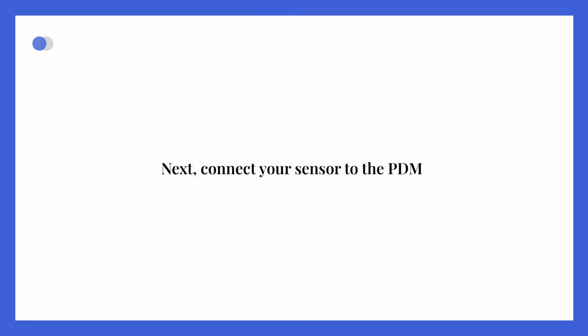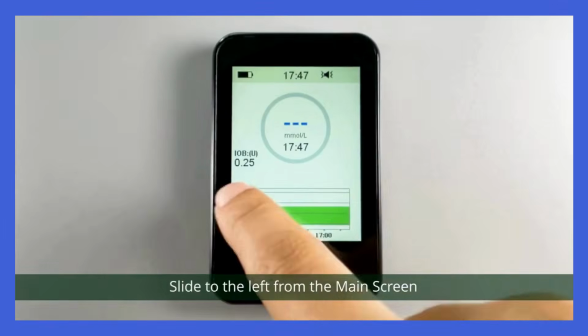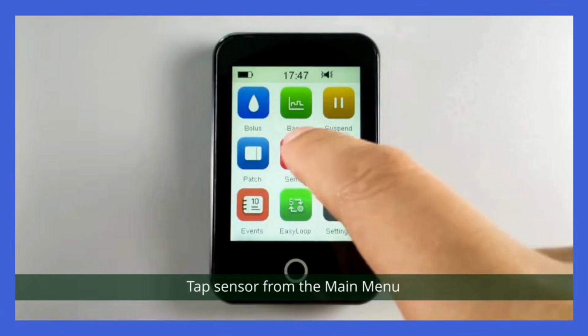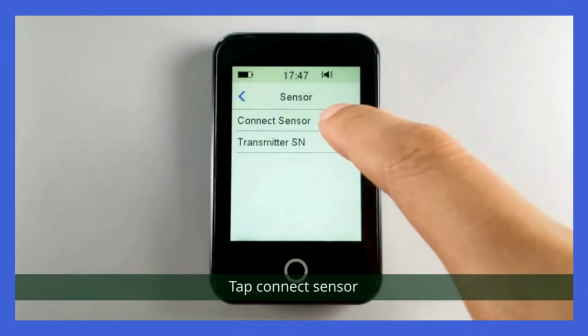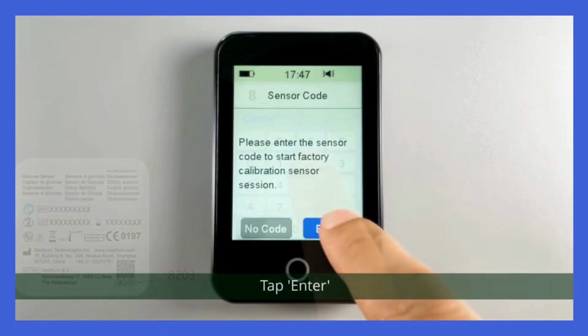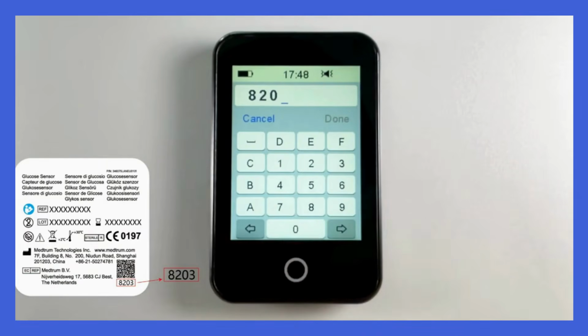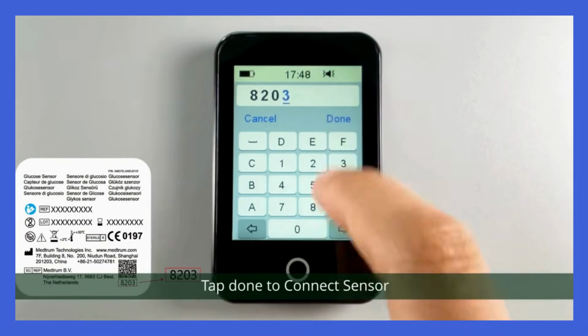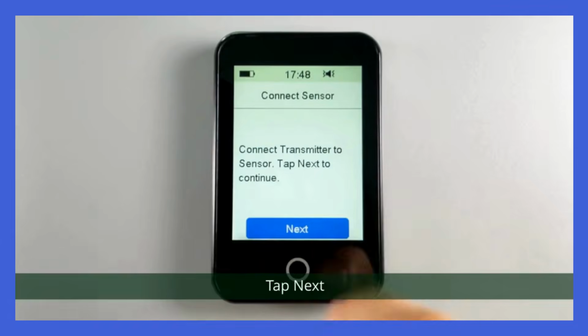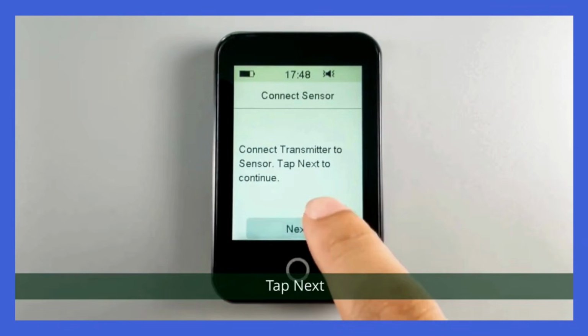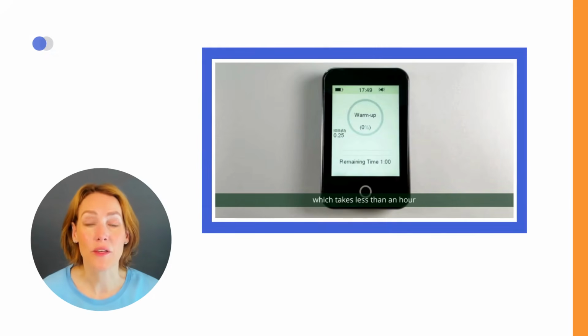Next, connect your sensor to the PDM. Slide to the left from the main screen. Tap Sensor from the main menu. Tap Connect Sensor. Tap Enter. Enter the sensor code from the sensor package. Tap Done to connect the sensor. Tap Next. Next, apply your TouchCare Nano sensor and transmitter on your skin if you haven't done so yet. After the warm-up, which takes up to 30 minutes, you will receive glucose readings.